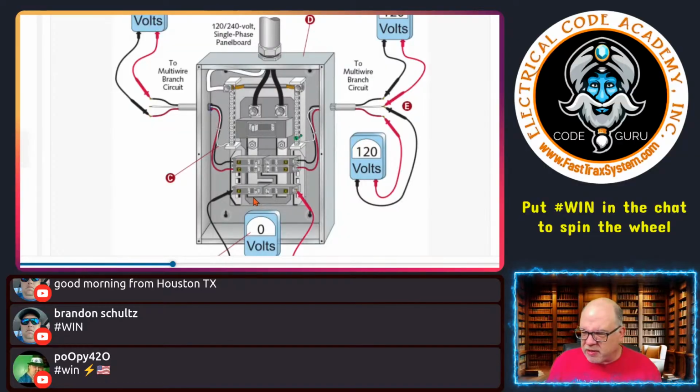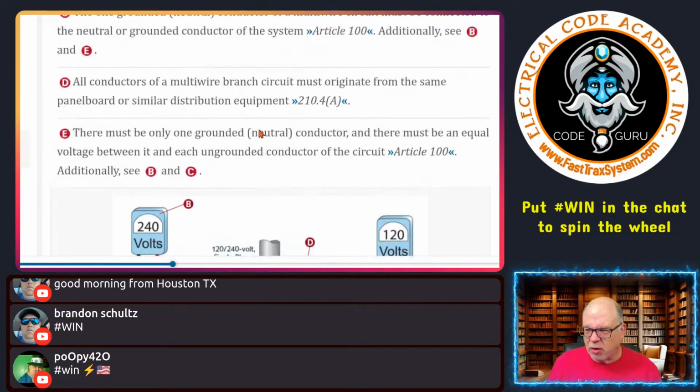The one thing you will notice here is it's either a 2-pole breaker, because remember, it's alternating. So this one and this one is the same leg. This is a different leg. This is the next leg. It alternates all the way down. So this right here is one. This is either an identified handle tie, which means it's 2 single poles side by side with a clip that goes over it that makes them operate simultaneously, or it's a 2-pole breaker, which will already have a common trip tie. So either way, you have multiple options to make this happen, but this is the only way a true multi-wire branch circuit functions. Truly the only way it functions.